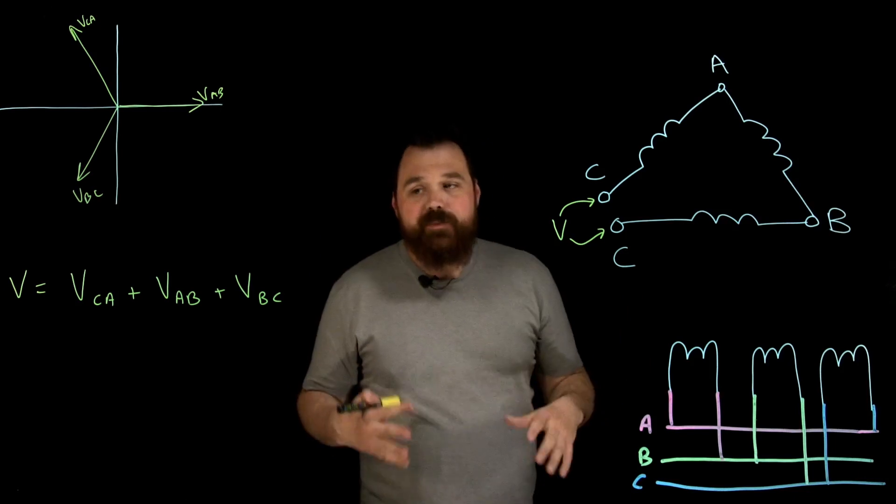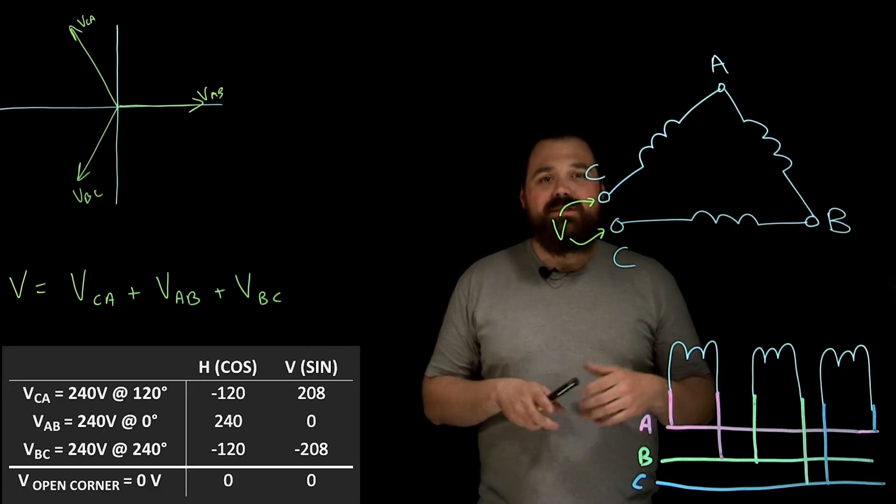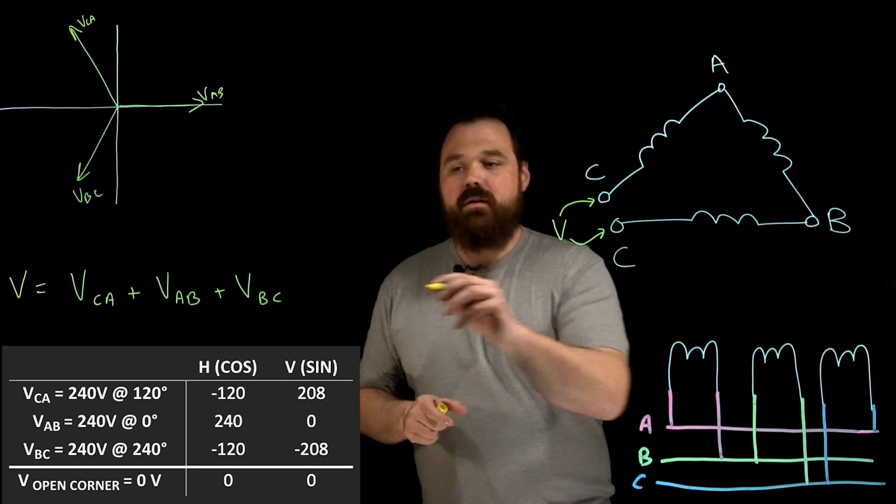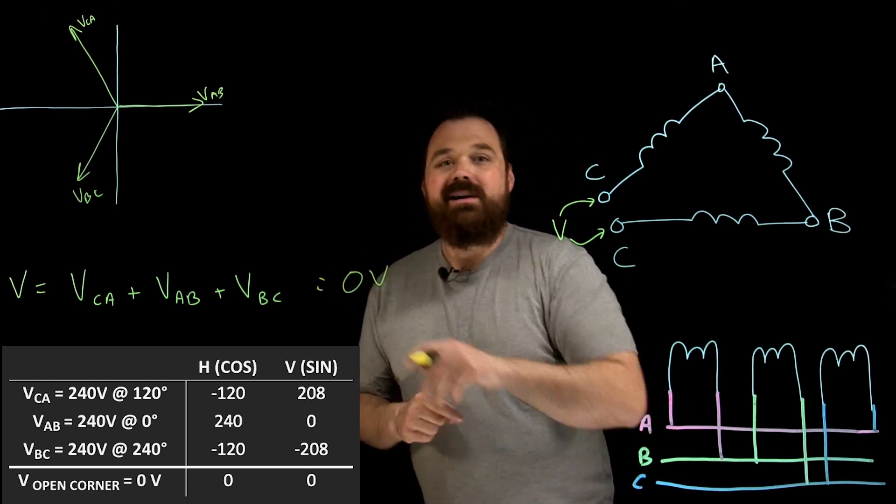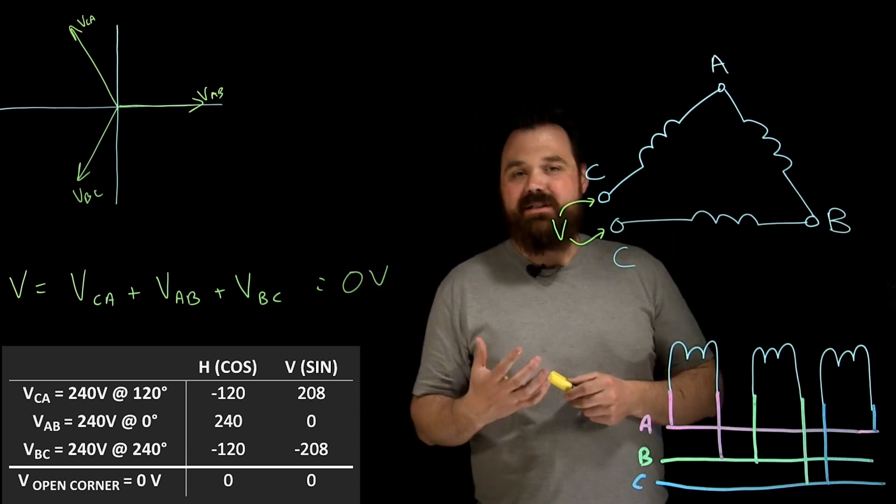When I add all that up, I get an HV chart. It would look something like this. And what we notice is that we get 0 volts. So we would say 0 volts is a proper connection. That's a good connection. That's what we want to see.